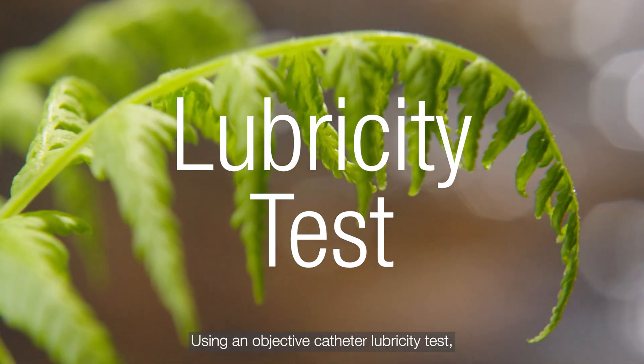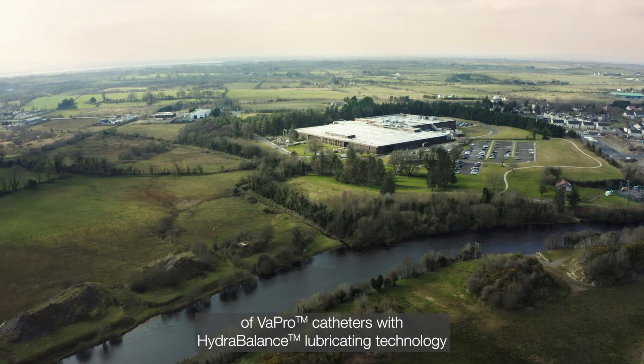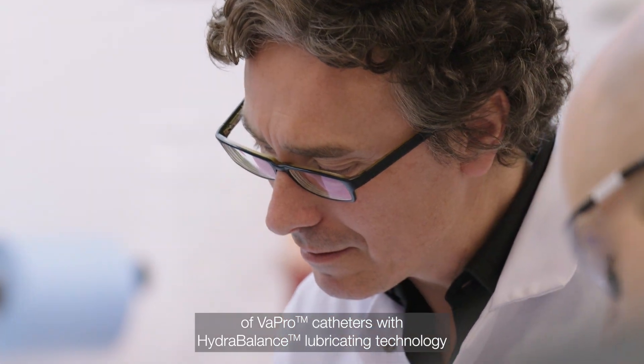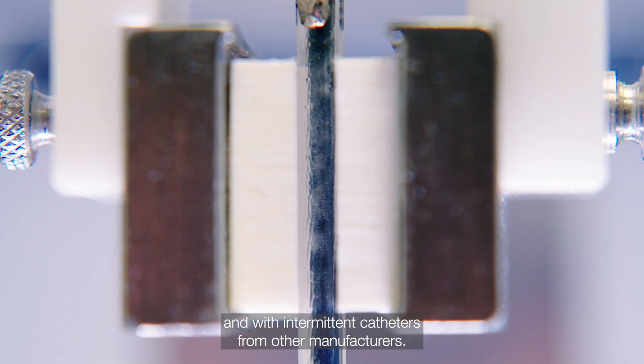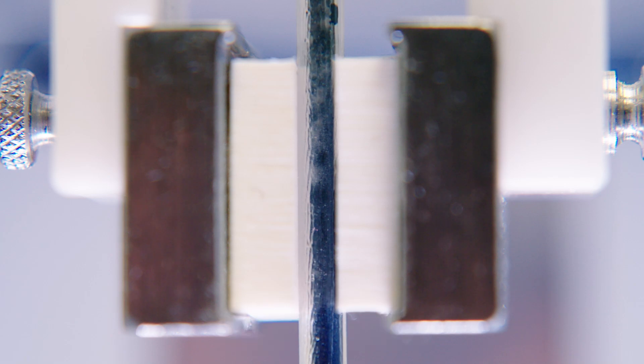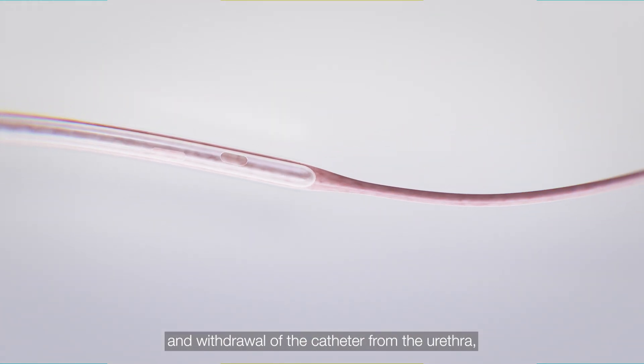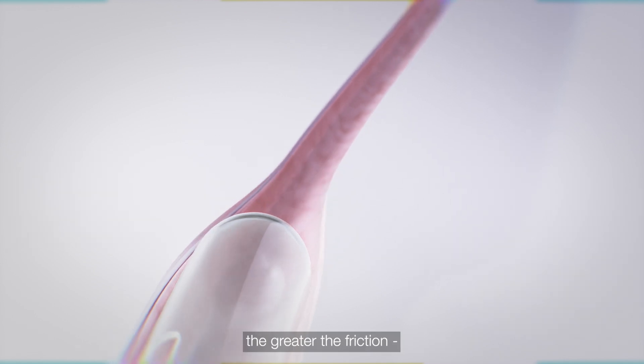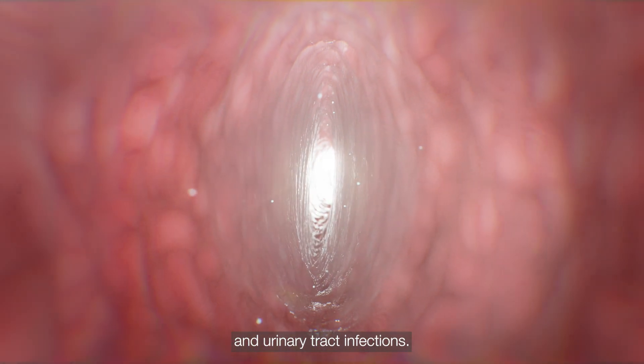Using an objective catheter lubricity test, Hollister compared the friction force of Vapro catheters with HydraBalance lubricating technology with the original Vapro catheters and with intermittent catheters from other manufacturers. The more force needed during insertion and withdrawal of the catheter from the urethra, the greater the friction, and the higher the risk of potential microtrauma and urinary tract infections.